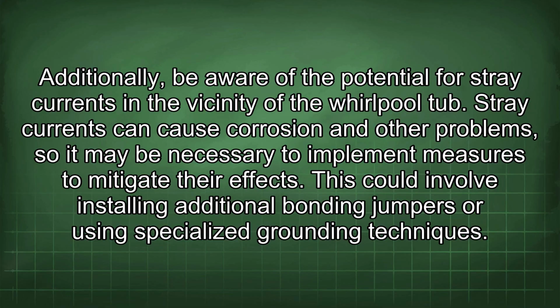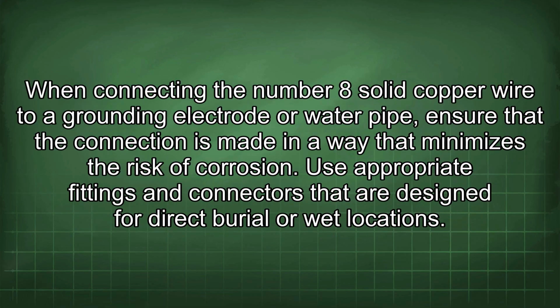Additionally, be aware of the potential for stray currents in the vicinity of the Whirlpool tub. Stray currents can cause corrosion and other problems, so it may be necessary to implement measures to mitigate their effects. This could involve installing additional bonding jumpers or using specialized grounding techniques. When connecting the number 8 solid copper wire to a grounding electrode or water pipe, ensure that the connection is made in a way that minimizes the risk of corrosion. Use appropriate fittings and connectors that are designed for direct burial or wet locations.